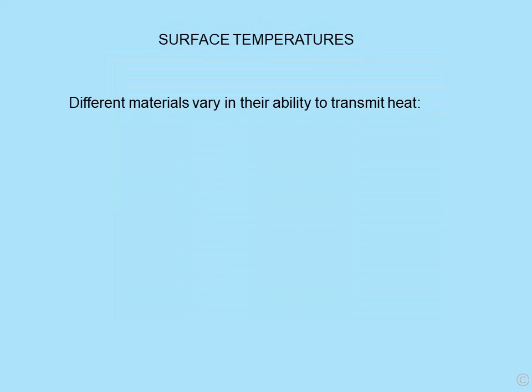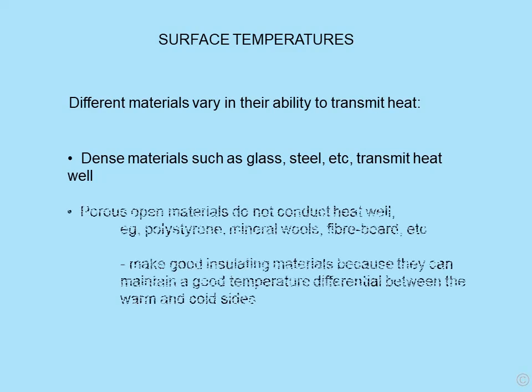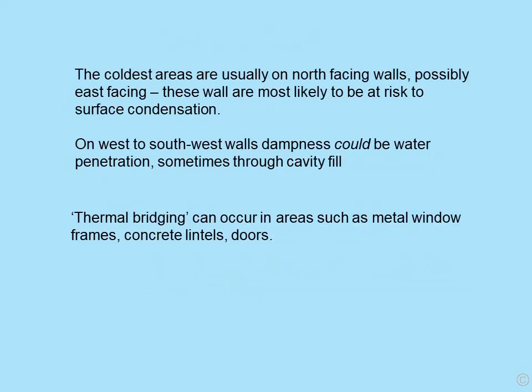Surface temperatures vary. Dense materials such as glass, steel and tiles transmit heat — and cold — well. Porous, open materials do not conduct heat well and make very good insulating materials, maintaining a good temperature differential between warm and cold sides. Coldest areas are usually on north-facing walls, possibly east-facing, and those are most at risk of surface condensation. On west to southwest walls, dampness could be water penetration, sometimes through cavity fill. Thermal bridging can occur at metal window frames, concrete lintels, doors and other structures.